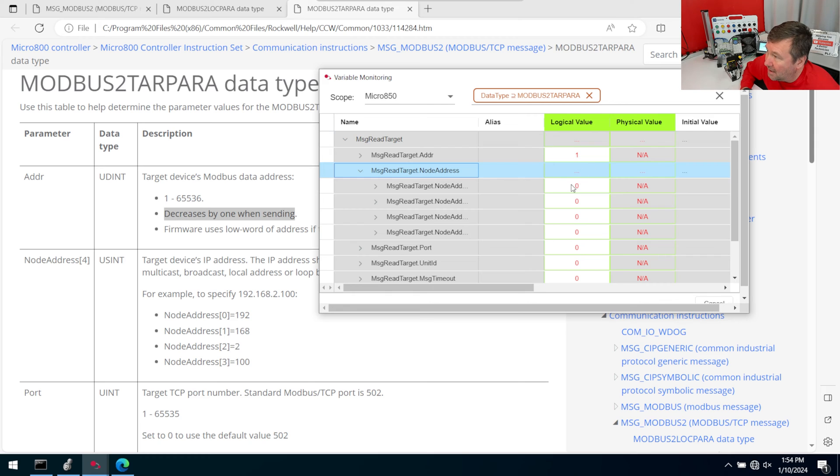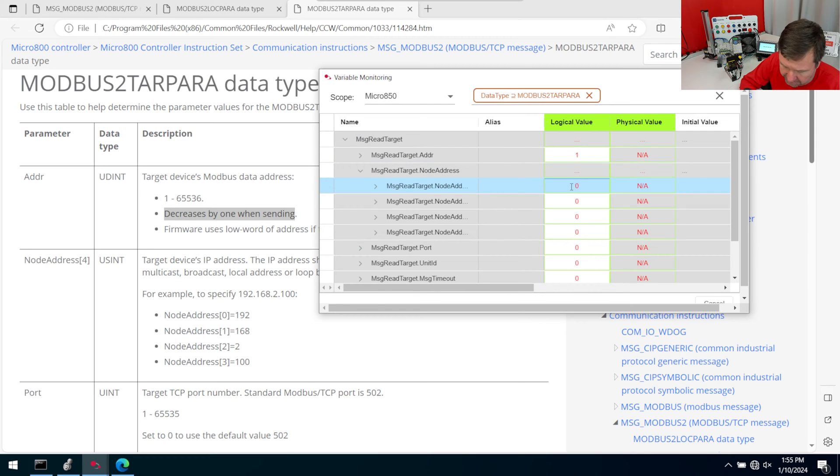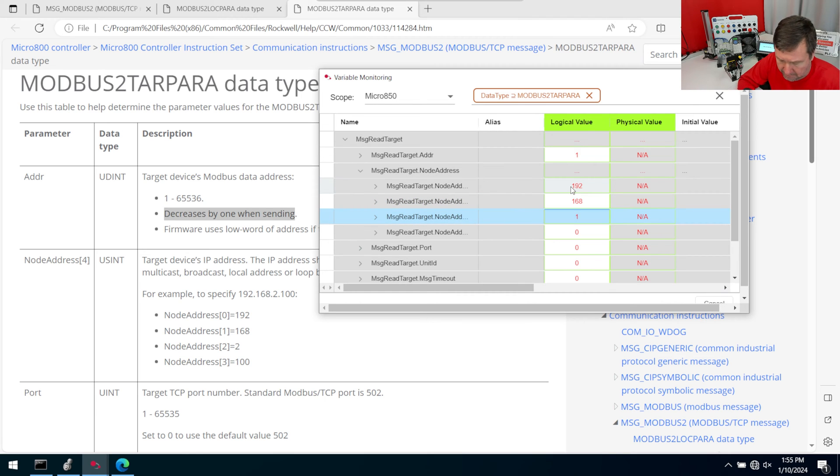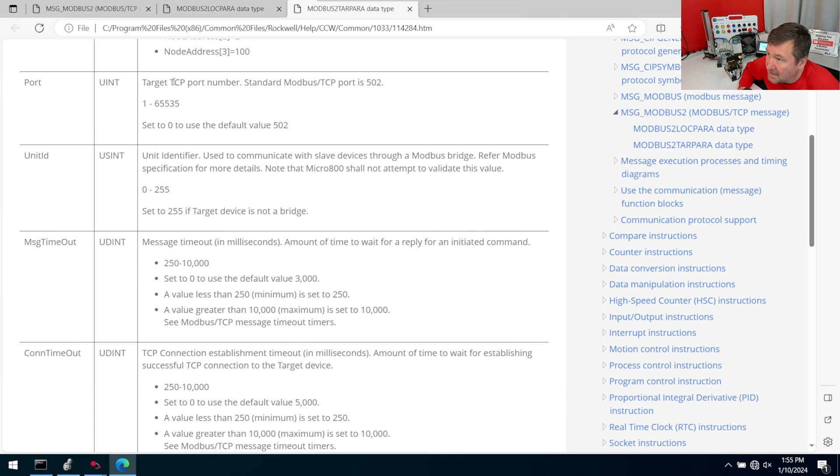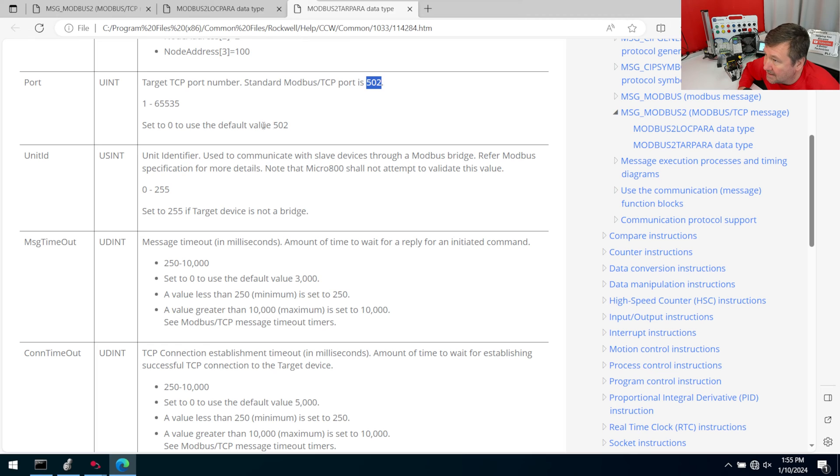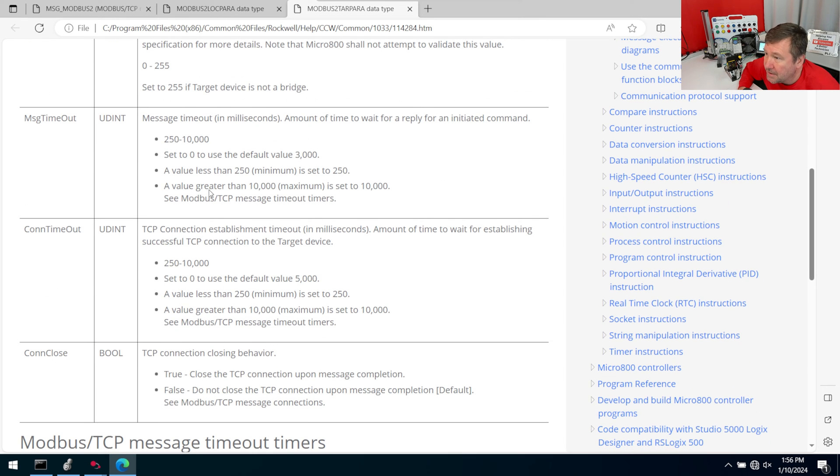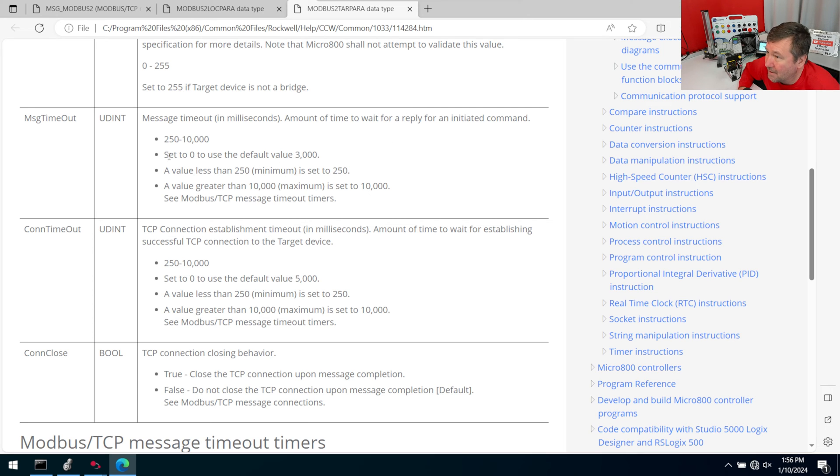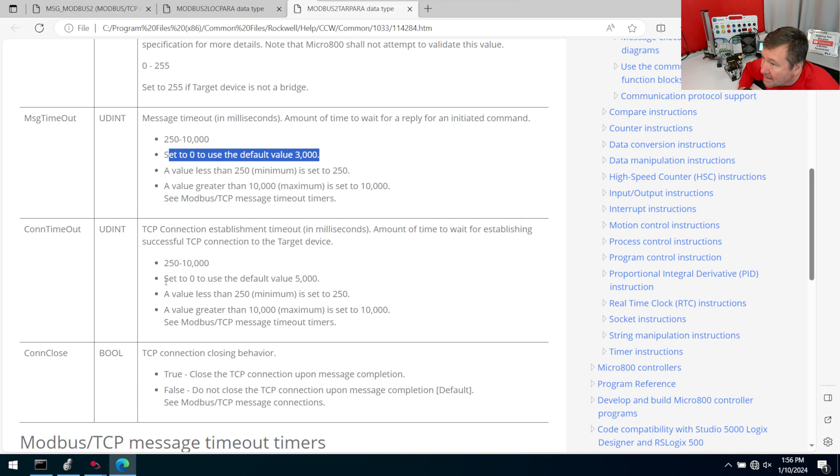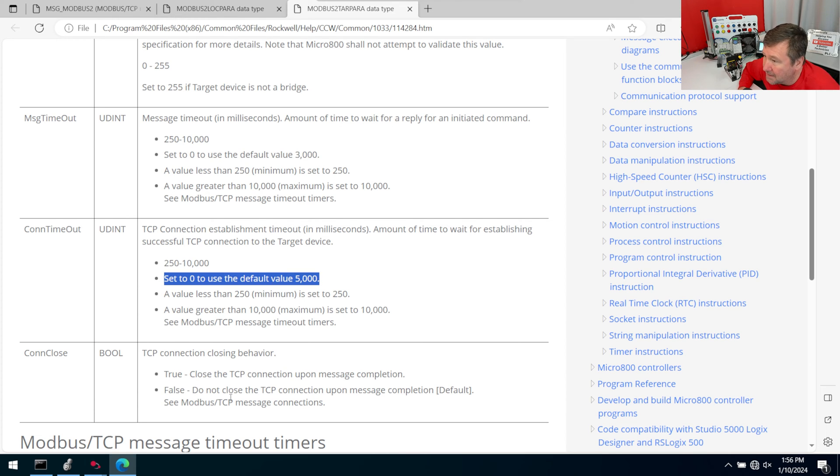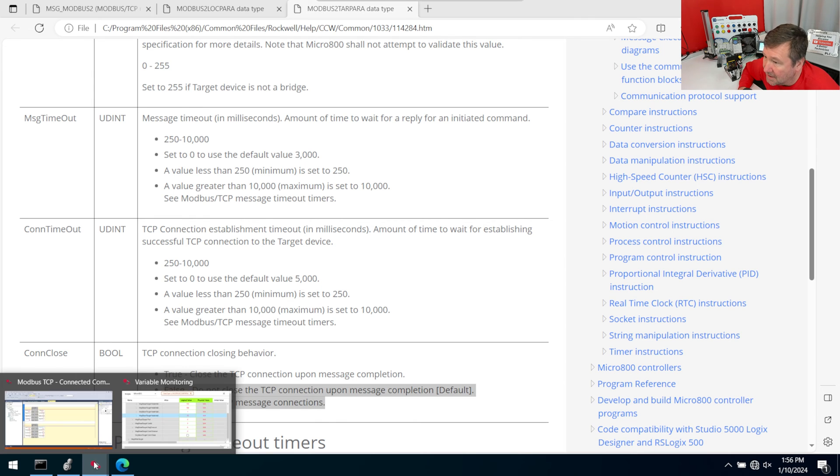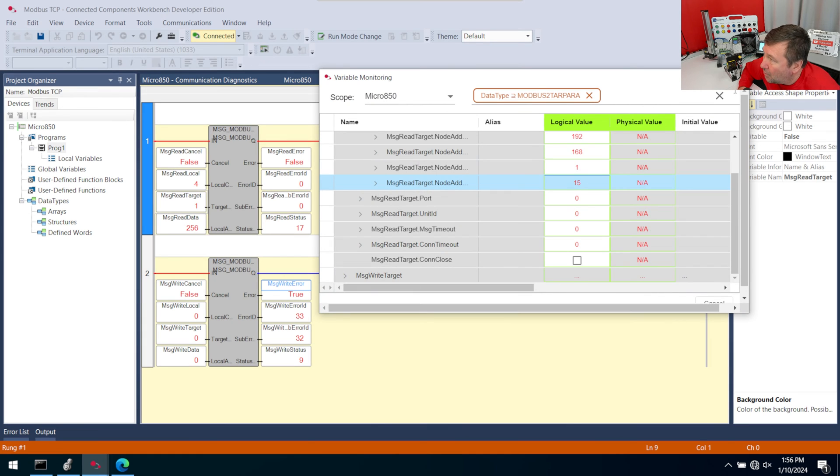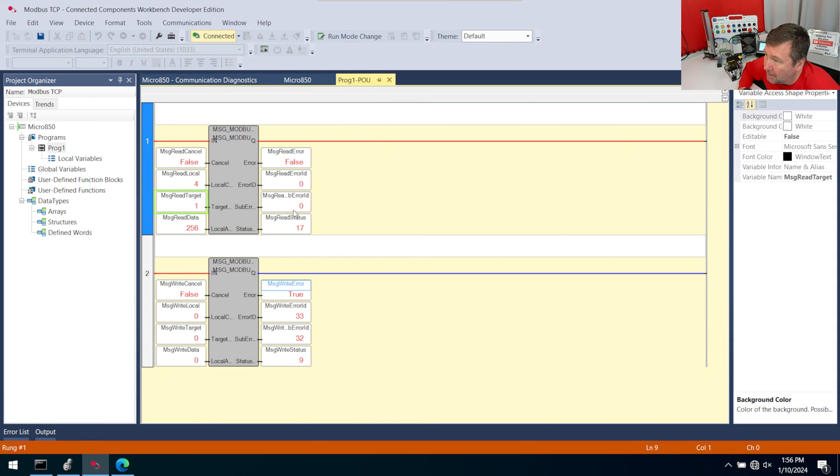And the next thing we run into is our node address. Now this is the IP address of our IO-linked module. And the default on our trainers is 192.168.1.15. We can actually leave the rest of these as they are typically. But let's explain them a little bit. The next thing we have is a target TCP port number. And the Modbus default is 502. And notice if you leave it at 0, it's going to be 502. And same with the next one. We can leave it at 0 because we're not doing any bridging. We have a timeout, which you may need to adjust later on. But the default usually works. And it says right here, set to 0 to use the default of 3,000. Same here, set to 0 to use the default of 5,000. And false means that we're not going to close the TCP connection.